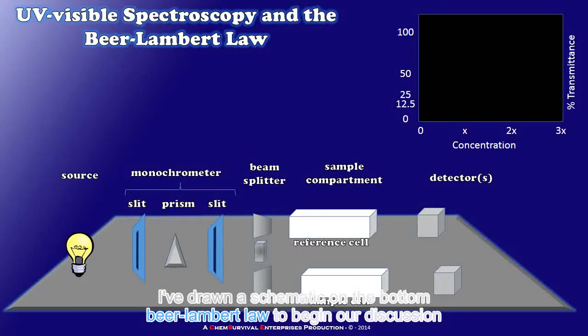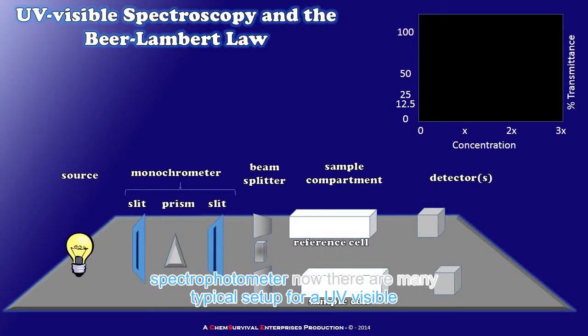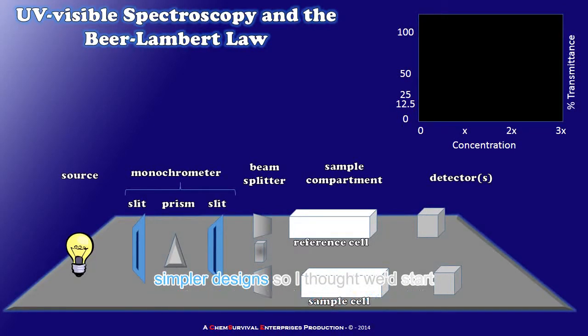To begin our discussion I've drawn a schematic on the bottom half of this screen depicting a fairly typical setup for a UV visible spectrophotometer. Now there are many different ways to build a spectrophotometer but this is one of the simpler designs so I thought we'd start there.